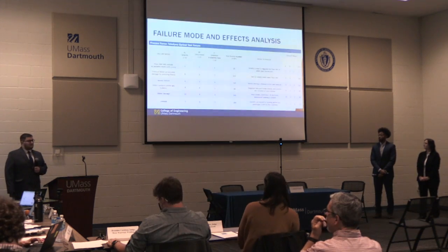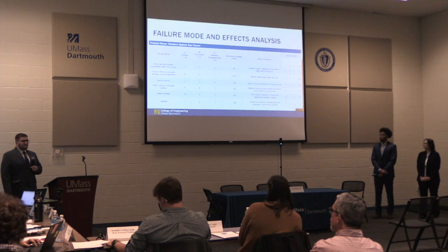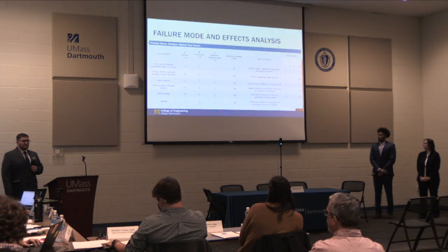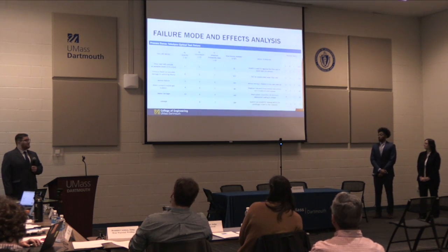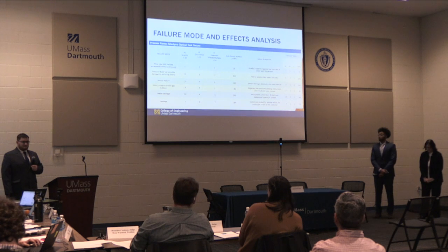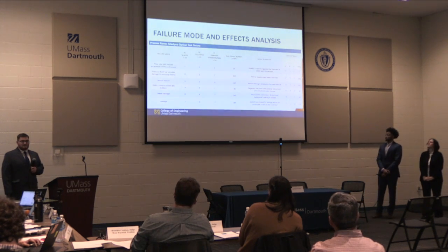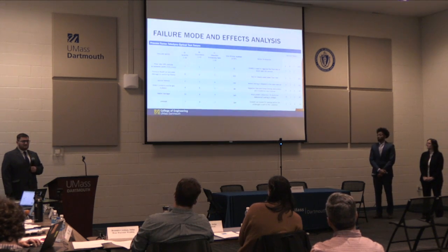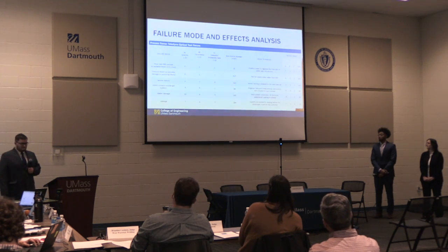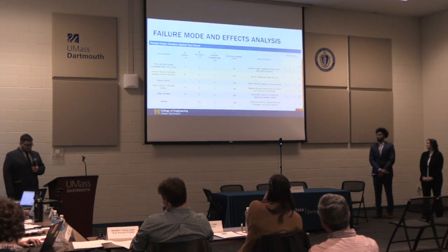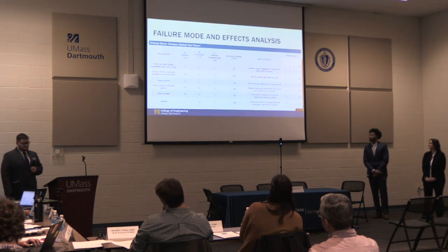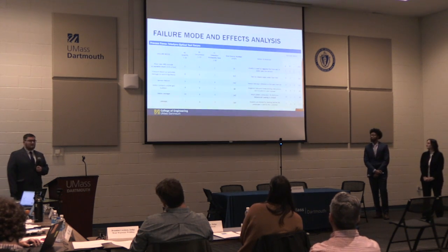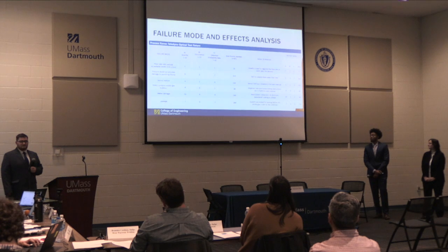That can cause clogging and pressure building. The pressure buildup can also damage components such as these filters, or any of our lines in the system can blow. Then we had sensor failure. It wasn't something that we expected to happen, but if it did happen, it would be a pretty severe case. Water containing any bubbles would just negatively impact our results. Our water clarity readings would not be accurate, and the water transmissivity would not be very high. Then we have water damage and leakage.